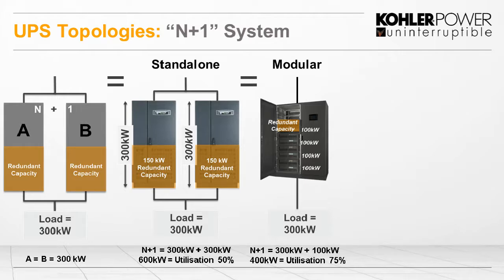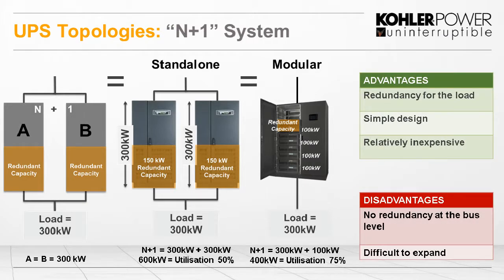So what we're looking at here now, we'll add it on the screen, is the utilization. Of course, on the 300 kilowatt, we now have two of them making 600 kilowatts, giving a utilization of 50%. If we make it up out of smaller modules, so the 4 100s, we have 400 kilowatts. So we're utilizing the UPS higher at 75%. And that becomes a little bit more important as we move on. So the advantages of N plus 1 is now we have redundancy for the load. So we can maintain one of the UPSs, one of the UPSs can fail, one can be taken offline, and we still have protection to the load.